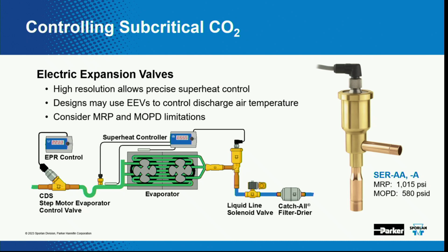This is the SER, and actually I've got one of these right here. It's an SERA. It's got an inline strainer built onto it, so you can unscrew that strainer and clean it out if you need to. All the advantages that you normally get with a stepper motor valve. You've got the high resolution for precise control. You're going to have to have a controller. There are some electronic controllers on here.